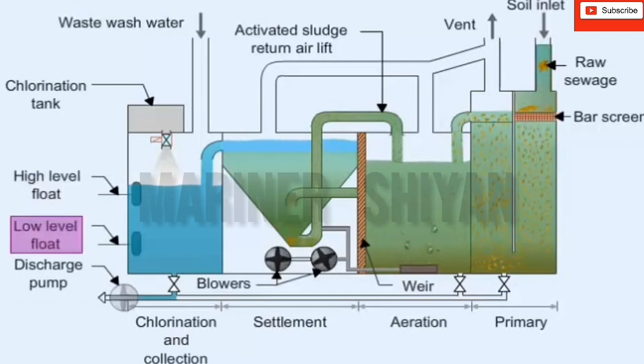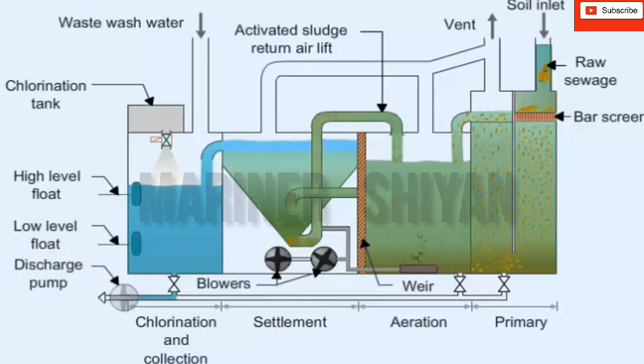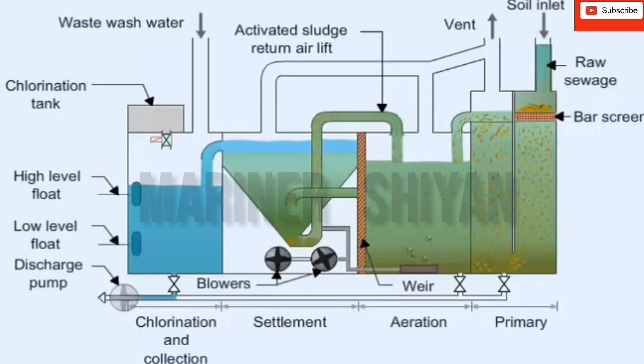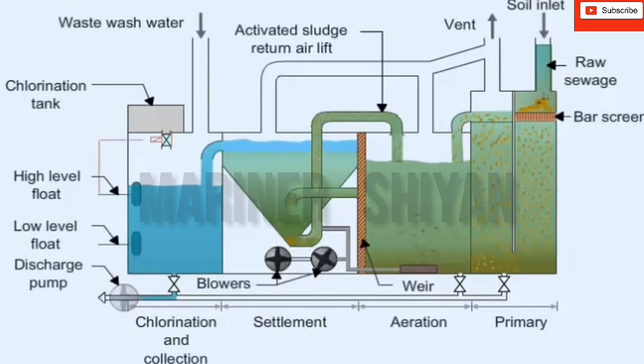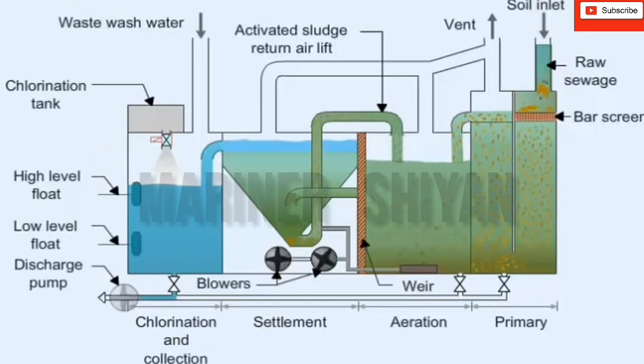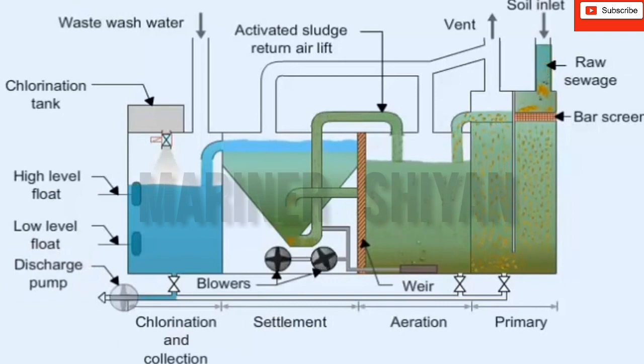Two float switches in the final section control the discharge pump. As the tank fills, the top float switch starts the pump. When the low-level float switch stops the pump, it simultaneously opens a solenoid valve in the water supply line to the hypochlorinator. In passing through the chlorinator, the water forms a sterilizing solution. A timing device on the solenoid valve allows the correct amount of solution into the treatment tank to deal with the next charge.